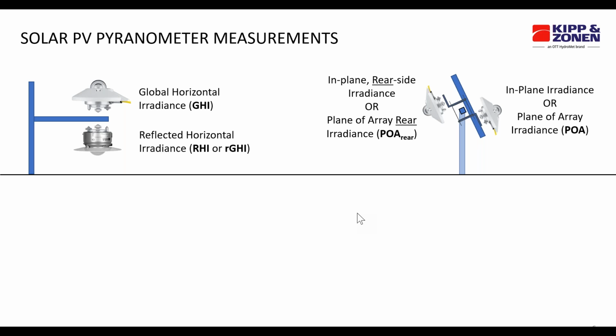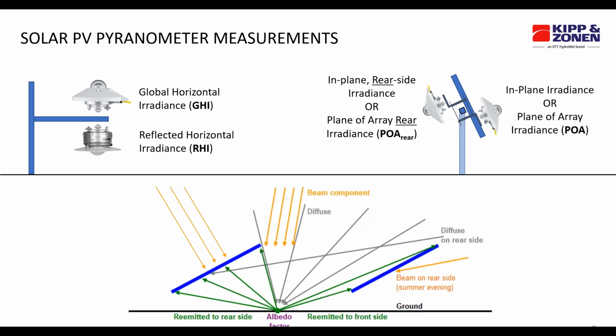Plane of array and rear-facing plane of array, or POA rear, sensors directly measure the total energy available for the modules to convert to electricity, rather than using the GHI value and albedo to estimate that energy with modeling such as PVsyst. We use these core sensors because we have to account for the irradiance reaching the modules from many different angles, and positioning the sensor within the site in the right locations around the module is a really important part of site design and installation.